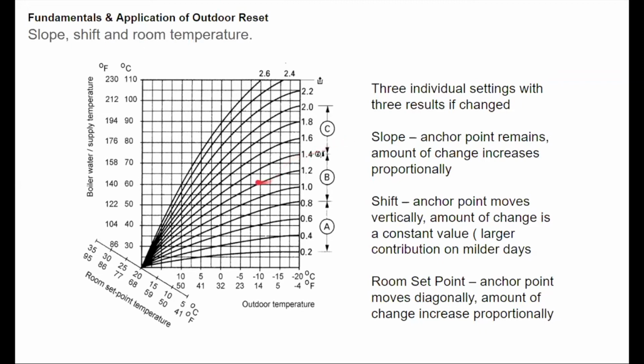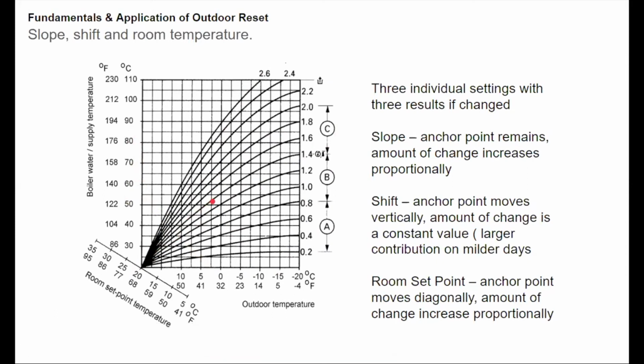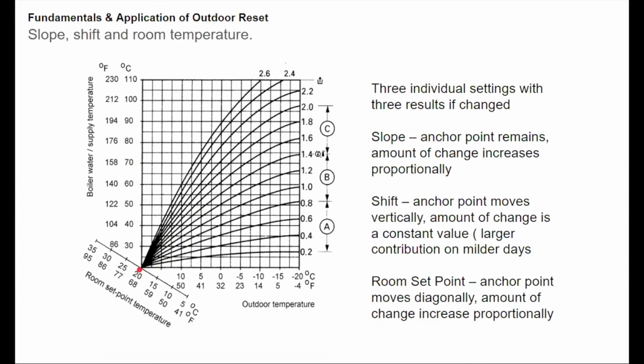So with the slope, what we're really doing is it's a curve, it's a shape, and it's a number anywhere from 0 to here we showed up to 2.6. And this sets the ratio, the change between changes in outside temperature and changes in water temperature. And what will happen is, as the outside temperature changes, the water temperature changes, and what that will do is it will potentially maintain a constant room temperature in that process. Okay. Now, I'm going to actually jump down to the bottom to room set point temperature.